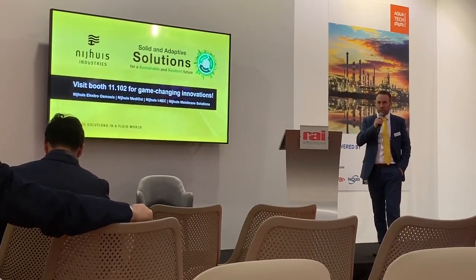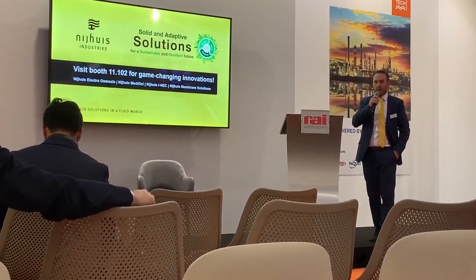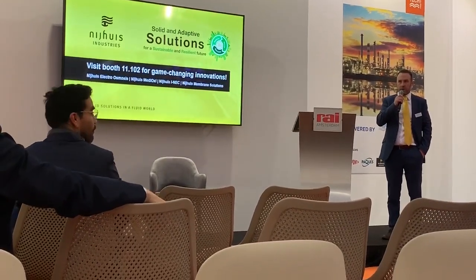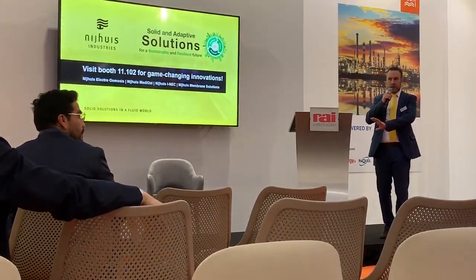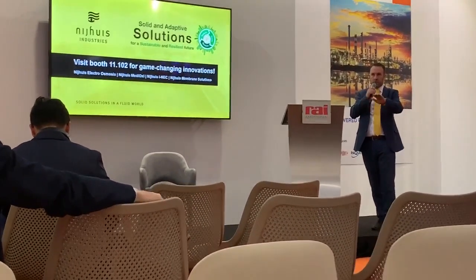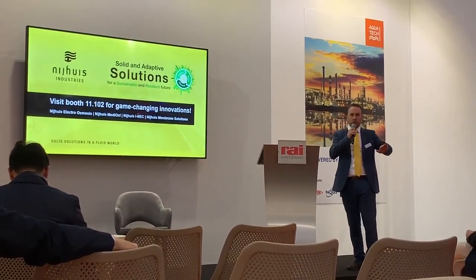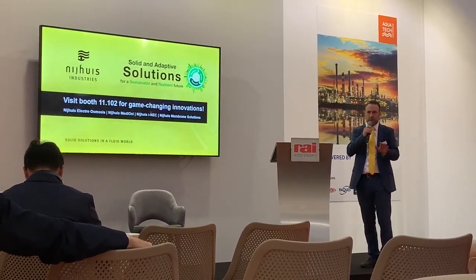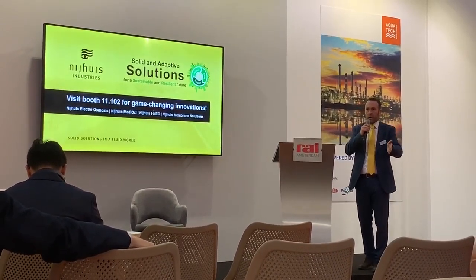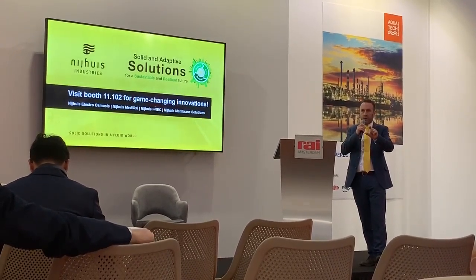Yeah. In the UK, 1 to 2 ppm of total oxidant in the cooling tower, and a minimum of 0.5 ppm free oxidant. So in this particular case, because the pH of the system is around about 9, we use bromine because the available oxidant is better. In more industrial cooling towers, particularly power, you probably use chlorine because you can control the pH a lot lower. But the net effect is the same. You still need that residual of 1 to 2 ppm.